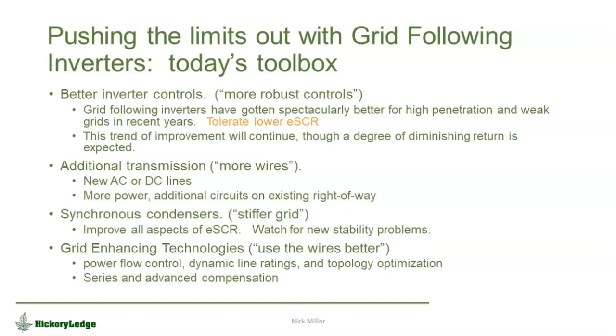You can add synchronous condensers, which improve effective short circuit ratio, but introduce possibly some transient stability problems. So we're seeing that two-edged sword manifest itself in different places, including Texas. And then there's different things you can do that aren't wires as such, but enhancement of the grid. So there's a bunch of tools that we have been using as an industry and continue to use to allow progressively higher levels of grid following inverters. But at some point, we need to do something different, and that's where grid forming inverters come in, and they are fundamentally different.